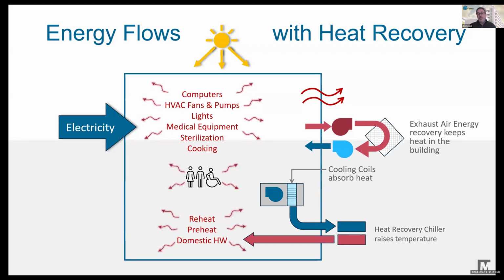In a system where we use heat recovery, we're able to capture that heat and reuse it. In an electrified building, we wouldn't have that hot water boiler—we might still have a steam boiler, or we might use electricity for steam. But all that power that goes into our building through electricity, we now recapture through a heat recovery chiller that makes hot water and sends it right back. We can do all of our reheating, preheating, and domestic hot water using recovered energy rather than burning gas to make new energy. An important part of that, particularly in colder climates or hot and humid climates like where I live in Atlanta, is to recover energy from the exhaust, which can significantly reduce the ventilation load.